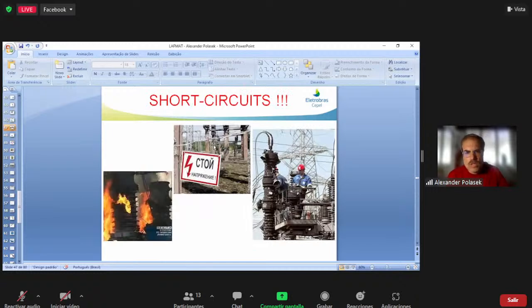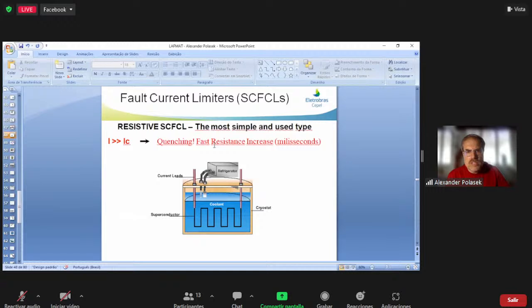Short circuits are also a big problem for the electrical grid, and sometimes the conventional protection devices are not able to prevent damage like that which you are seeing. And so fault current limiters are also a very promising application. Here I'm just showing you the most simple and most common one. There are also other kinds of fault current limiters. The idea is that if you have a superconductor in series with the line, in line with the grid, during normal operation, the impedance is very low, it's negligible. And when you have a short circuit, it quenches.